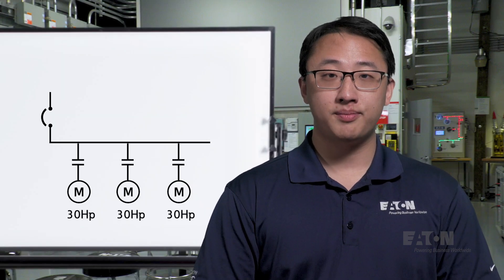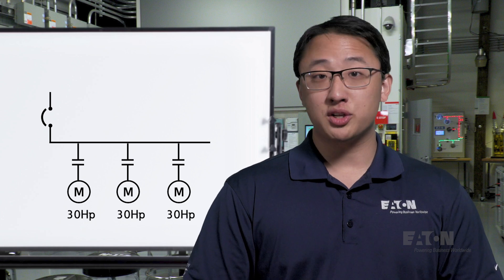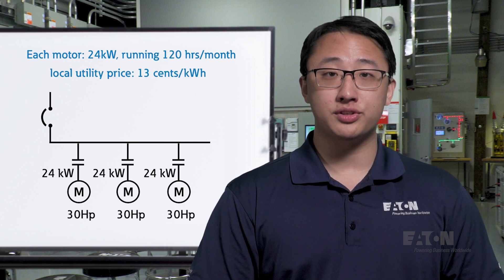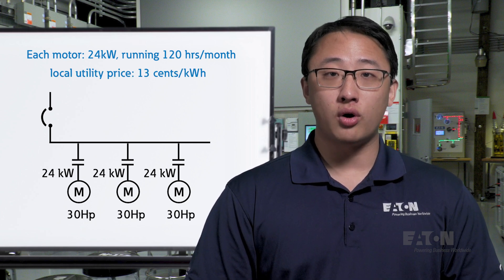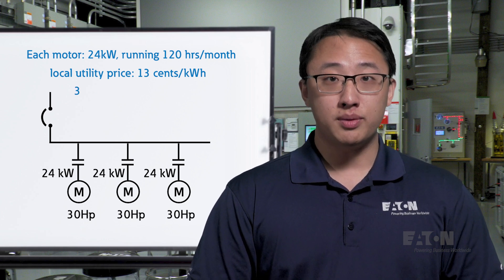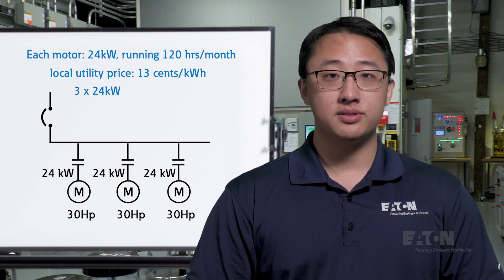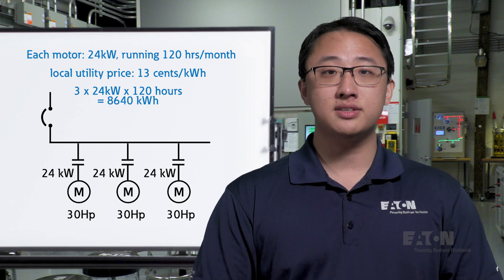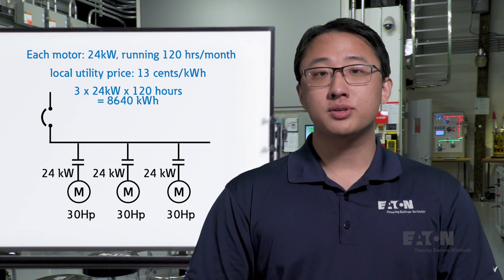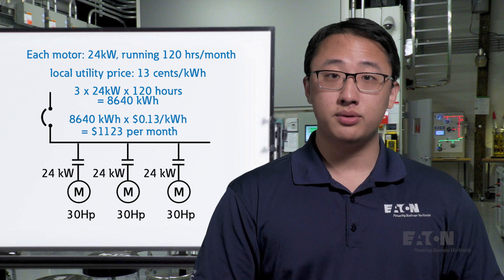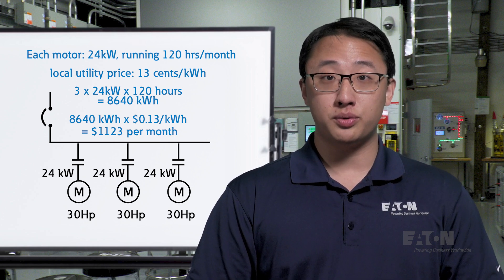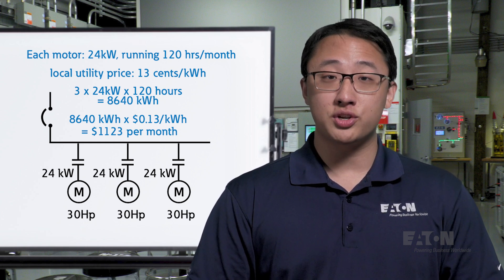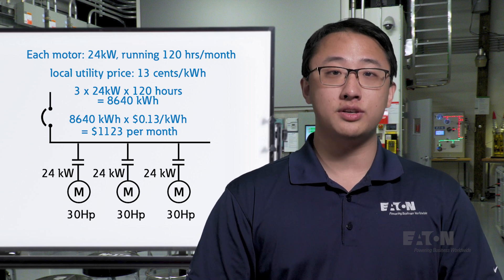Now it's time to talk about energy and money. If each motor uses about 24 kilowatts and is running on average 120 hours a month, and the local utility price is 13 cents per kilowatt-hour, then the energy used per month for all three motors is calculated as: 3 motors × 24 kilowatts × 120 hours = 8,640 kilowatt-hours. Multiplying by 13 cents per kilowatt-hour gives $1,123 per month. You can imagine why it's so important for industrial facilities, which have many more and much heavier loads, to find ways to use less energy to save money.